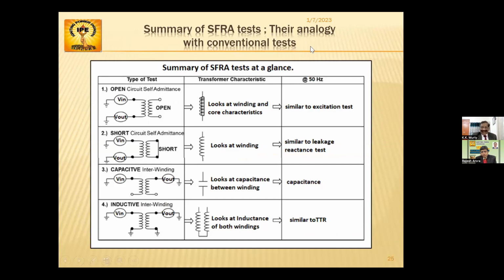Now, this is the summary of the SFRA, which has an analogy with the conventional tests. This is just a summary. The open circuit test is similar to the excitation test. Similarly, the short circuit test is similar to the leakage reactance test. This is the capacitive interwinding test, similar to the capacitance test. And this inductive interwinding test is similar to TTR, transformer turn ratio. This I will show you in the upcoming slides, how it is used for finding out the turn ratio.